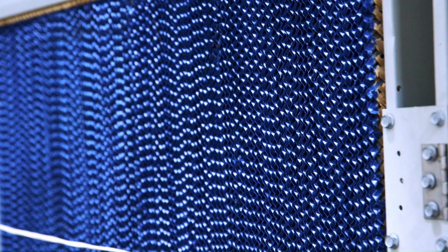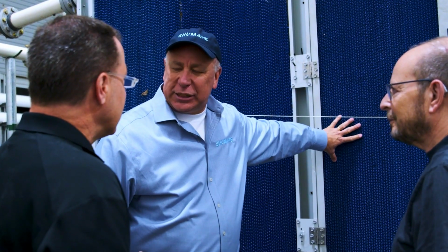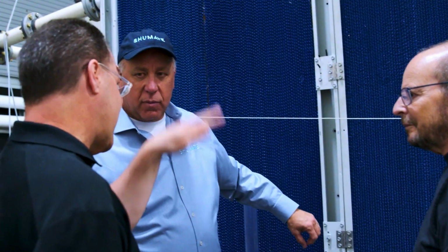So right now we're at the BAC test lab, and they have a Trillium product in the test lab where they can simulate the extreme weather conditions that we need for proof of concept for this product as part of a design for a mission critical project. During today's operation, we're running through several different test scenarios at some temperatures set up for a data center design to ensure it can meet the leaving water temperatures required for both dry operation and wet or adiabatic operation.